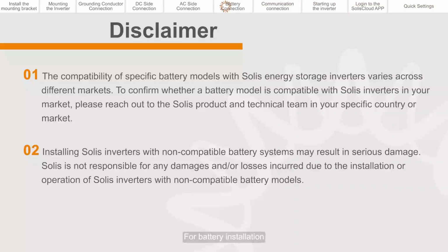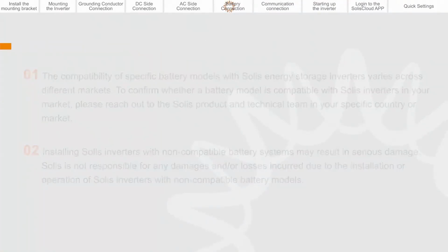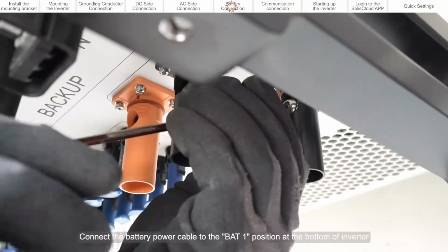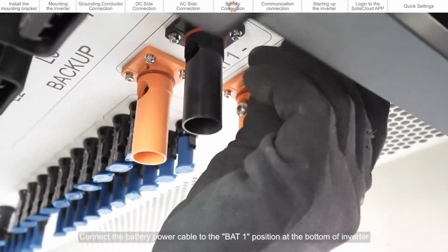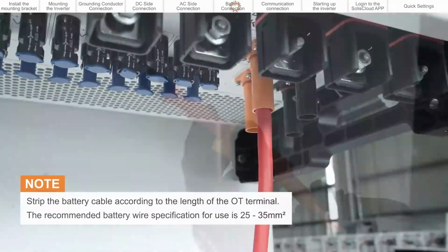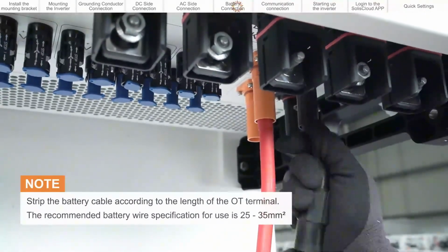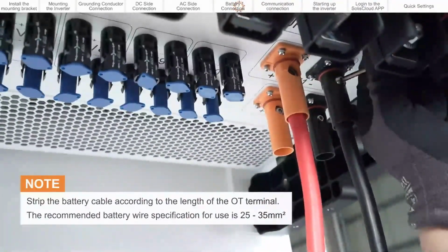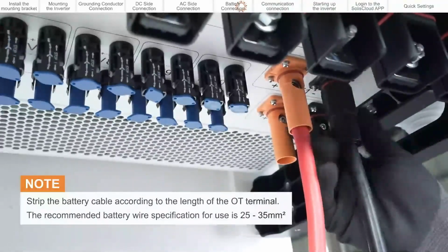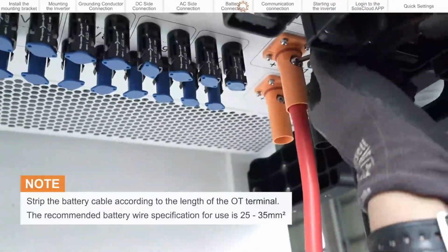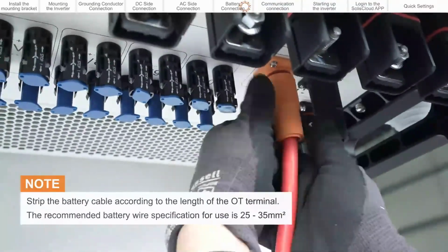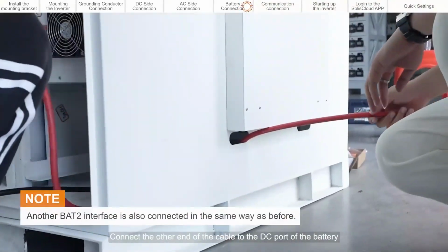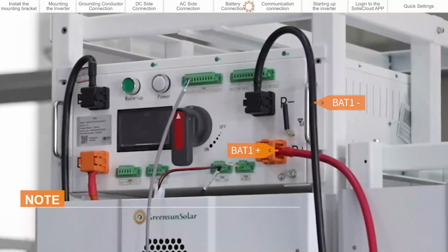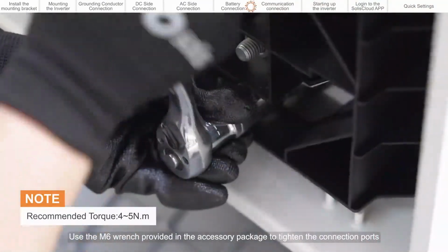For battery installation, please refer to the battery manufacturer's installation instruction manual. Connect the battery power cable to the BAT1 position at the bottom of the inverter. Connect the other end of the cable to the DC port of the battery. Use the M6 wrench provided in the accessory package to tighten the connection ports.